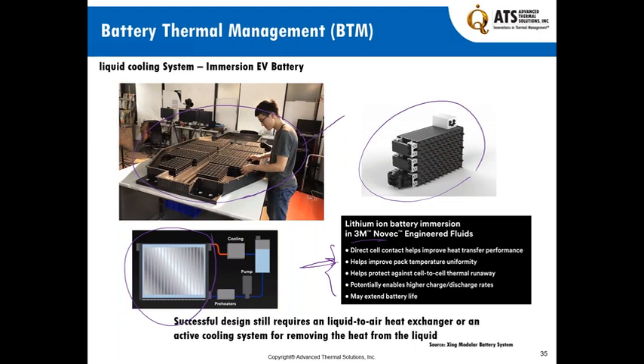So a successful design requires a liquid-to-air heat exchanger or an active cooling system to remove the heat and create the recirculation required. We have a phase change from vapor to liquid, so we never have a dry out. If your liquid-to-air heat exchanger fails, you're going to have a dry out — all the liquid inside the immersion system will vaporize, and as a result we may have all kinds of catastrophic failures.